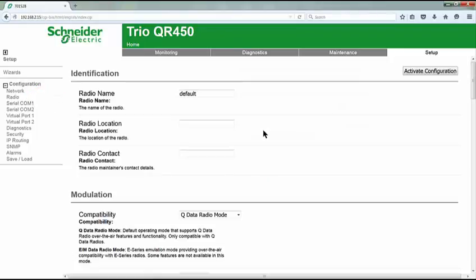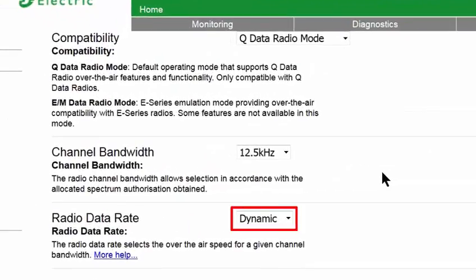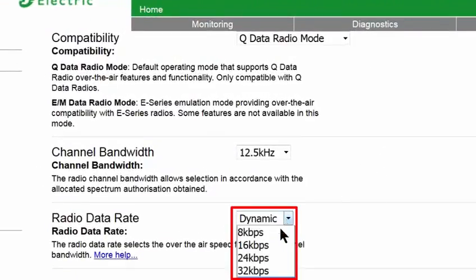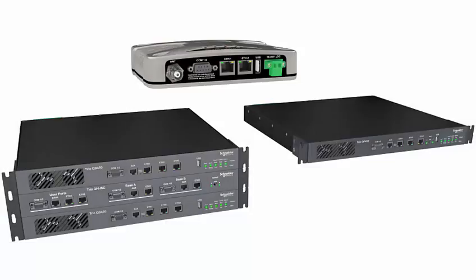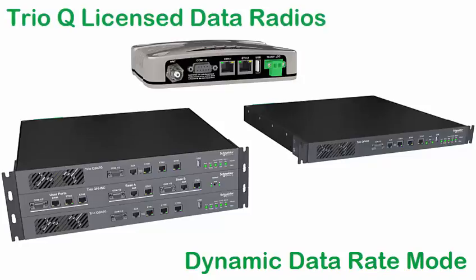Scrolling down to the modulation area, it can be seen that the radio is by default in dynamic mode. So, in fact, there is no configuration at all required to place TRIO Q-Series radios into dynamic mode. There are several fixed data rates available while in this 12.5 kHz channel bandwidth — 8, 16, 24, or 32 kilobits. Just remember that if a fixed data rate is preferred, all radios in the system must be configured for the same data rate. Thank you for watching this video discussing the dynamic data rate mode available in the TRIO Q-Series licensed data radio.